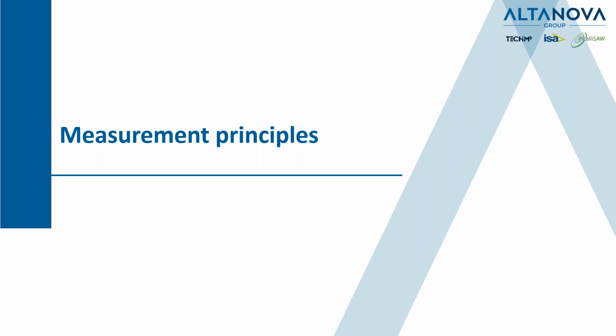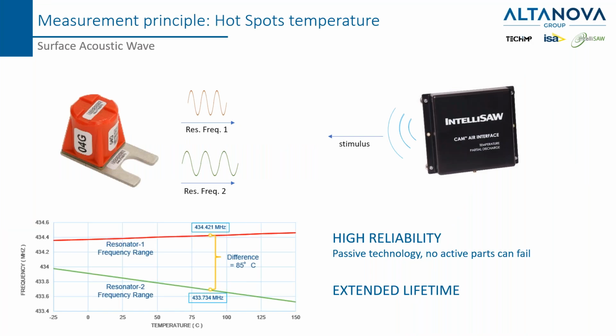A few words about the measurement principles of this system. Basically, we take as an example the standard IntelliSAW sensor for the medium voltage compartment. This sensor is using the so-called SAW technology, that means surface acoustic wave. To simplify the principle of this system, we could say that the antenna interface is continuously sending a signal to the sensor that we call a stimulus. You have to imagine everything inside the medium voltage compartment.